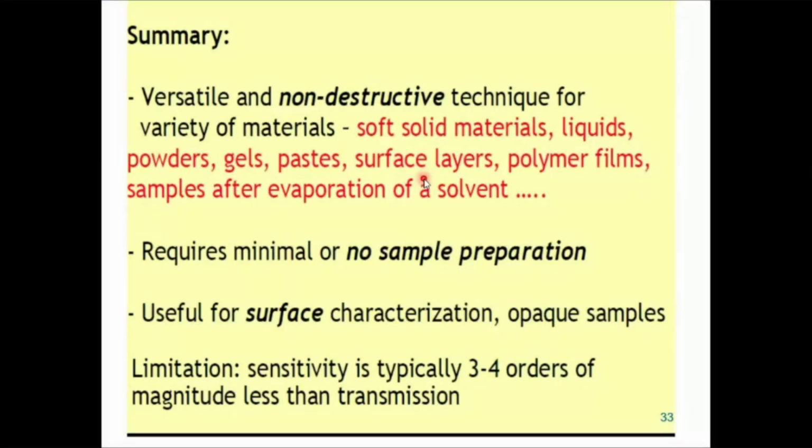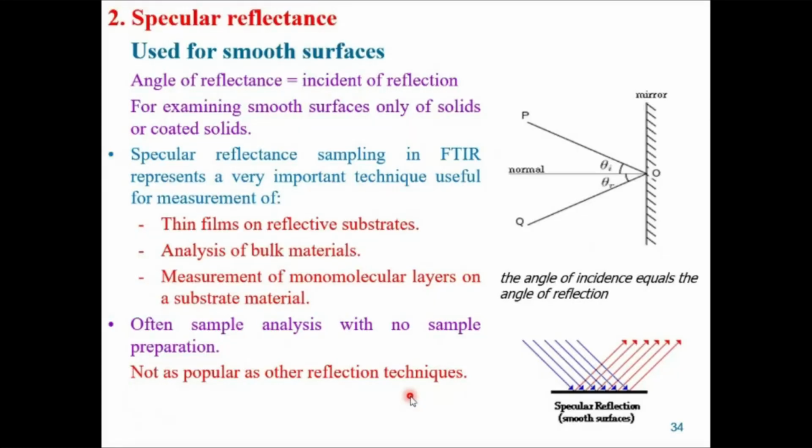So in summary, if you talk about ATR, it is a very versatile, non-destructive technique for a variety of materials. It requires very little or almost no sample preparation. It is used for surface characterization and opaque samples. It has limitations also. Sensitivity is typically 3 to 4 orders of magnitude less than transmission because the number of molecules interacting with IR is less. Now, ATR is done.